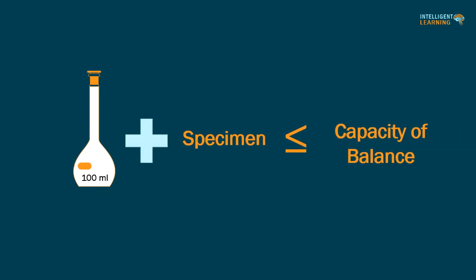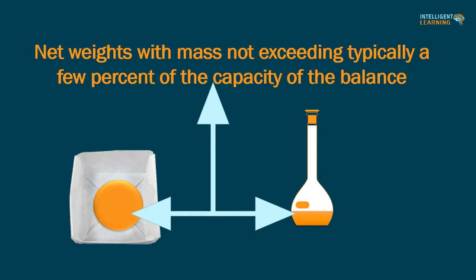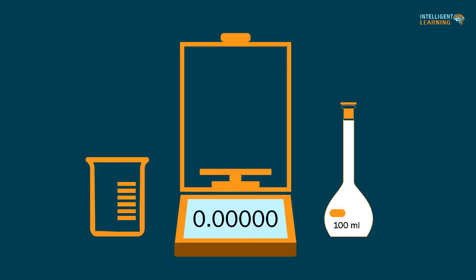Total weight of the receiver plus the specimen must be less than the capacity of the balance. A properly maintained and adjusted laboratory balance has weighing uncertainty for small masses. Net weights with mass not exceeding typically a few percent of the capacity of the balance are essentially determined by the repeatability. Repeatability depends on the size and surface area of the weighed object.